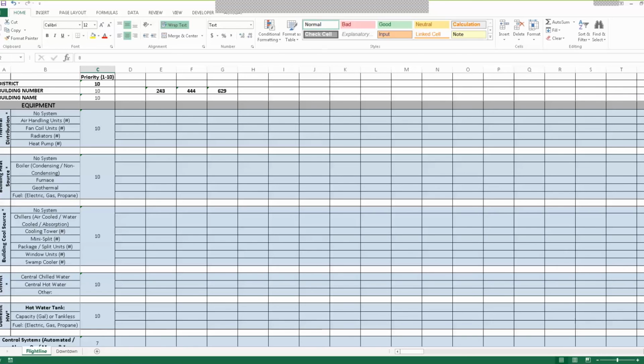But if you're in that system where they've taken, let's say, an old multi-zone, and they've made it into a quasi, they've taken out the dual deck stuff and made it single decks, I don't want to use any harsh adjectives for that system, but they tried to modernize it without having to rip all the equipment out, so they blank stuff off and things. You'll see things like that happening, and so getting a feel for that is always helpful.